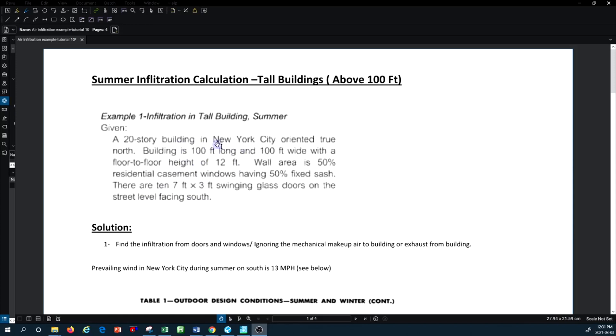Quite a bit of information is provided in this example. We need to find relevant data and correction factors from standards. For this example, you need tables from the ASHRAE Fundamentals standard and the Carrier HAP handbook, where you can find all the tables and information used here. I'm presenting portions of those tables to show how to make this calculation for air infiltration through a tall building in the summertime.